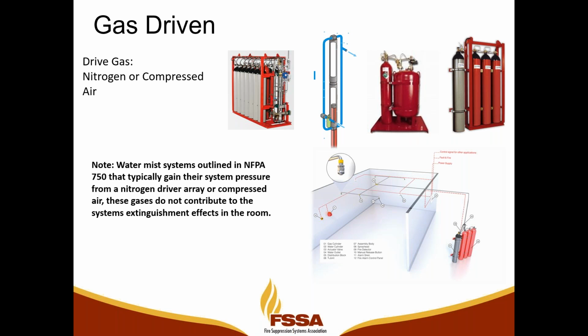that then break the molecules up into the small particulate called water mist. Now, one thing to note in gas-driven systems that is different and defined in NFPA 750 is that any gas-driven system that typically gains its pressure from a nitrogen driver or compressed air array will not have the nitrogen or the compressed air contributing to the extinguishing effects of the room. So basically, the nitrogen or the compressed air that's used is strictly there to drive the pump. It's not there to reduce oxygen levels in the room or be a key or major extinguishing principle in extinguishing a fire in a particular hazard. Next slide.